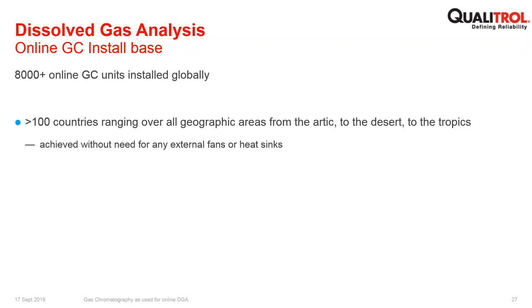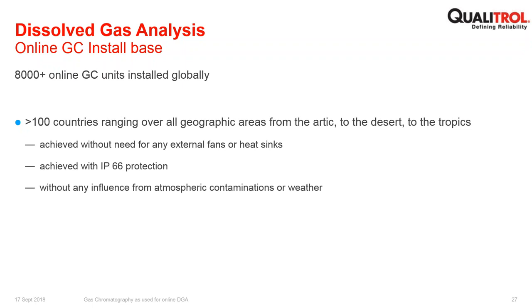This means that this system can be operated without any need for external fans or any need for heat sinks. So there's no need to dump heat out of the monitor, because the monitor operates hot continuously. This allows for IP66 protection, because you can have a completely sealed system. There is, of course, no influence from atmospheric contamination or weather, because the system is sealed from a gas perspective also.